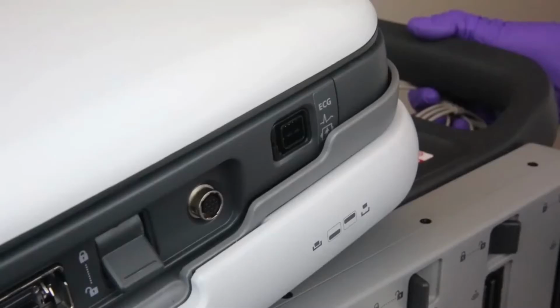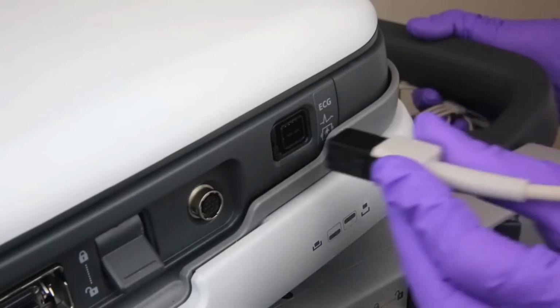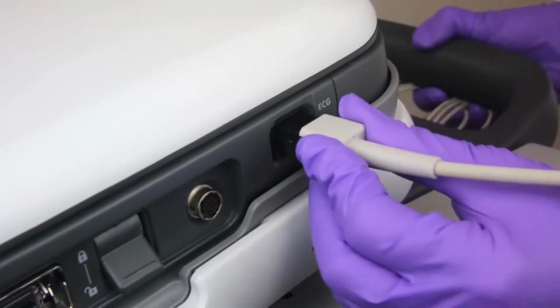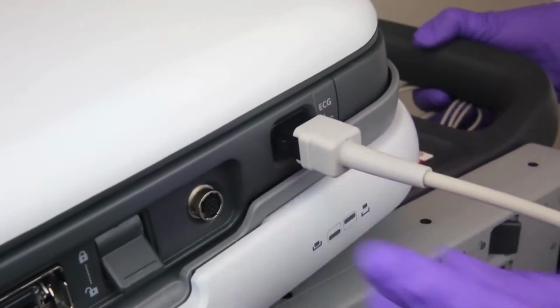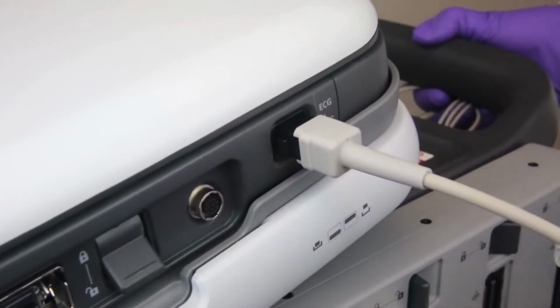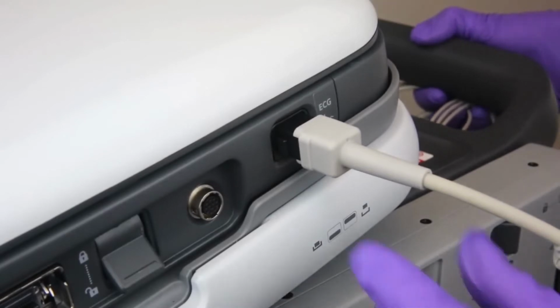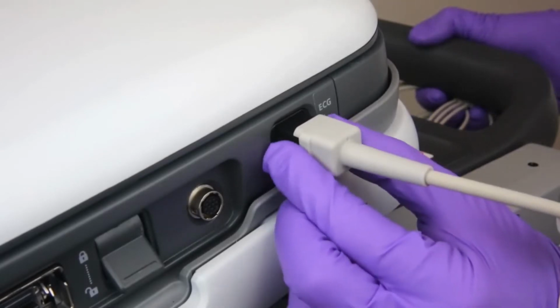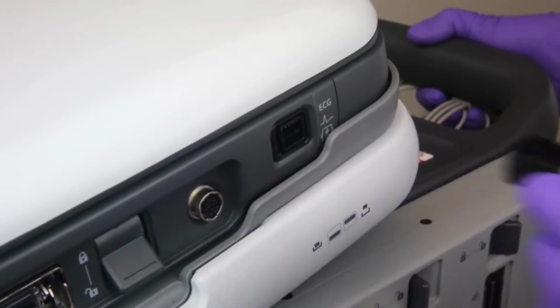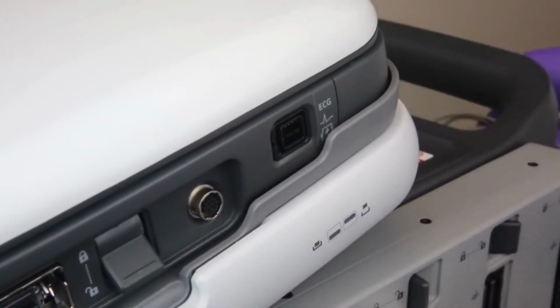The ECG physio port is located next to the transducer connector. To connect, match the plug and pins and then gently press until you hear a click. To remove the ECG physio cable, press the button on the cable connector located towards the front of the system. Gently pull the cable out of the plug.